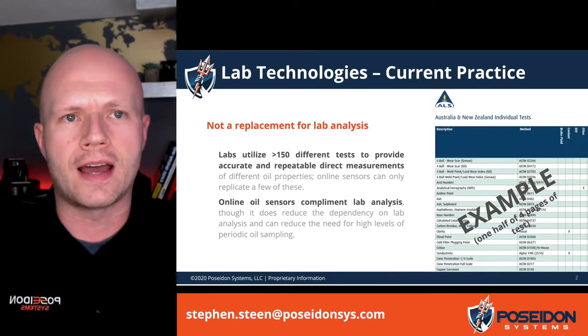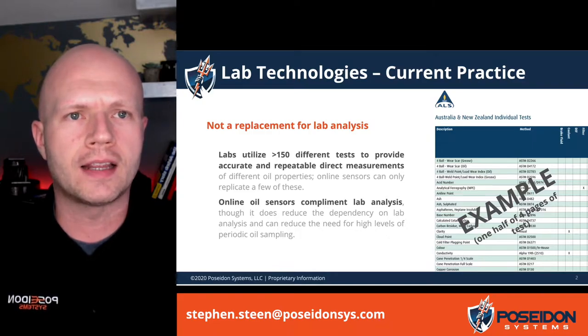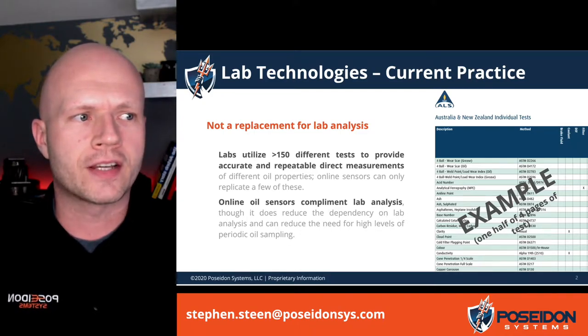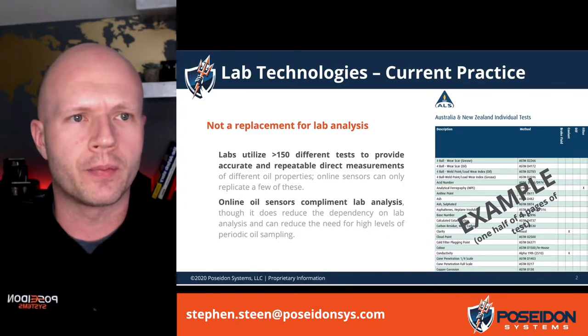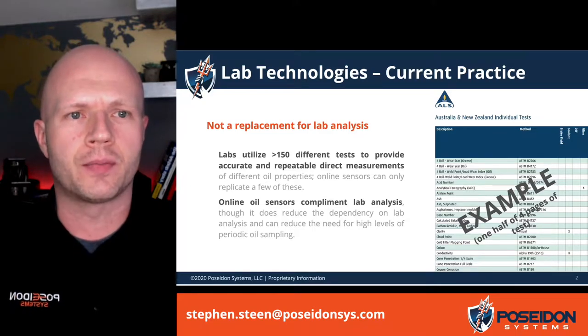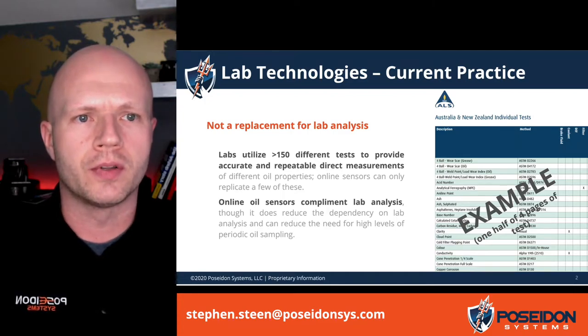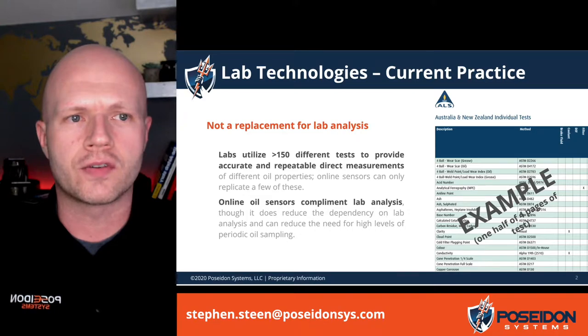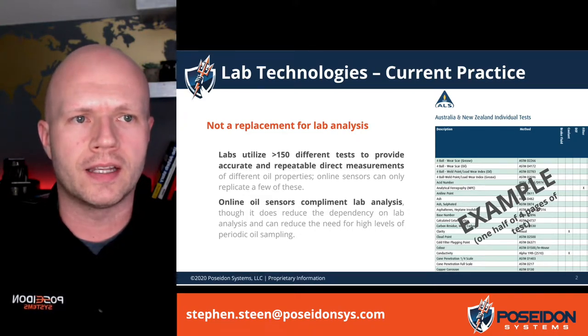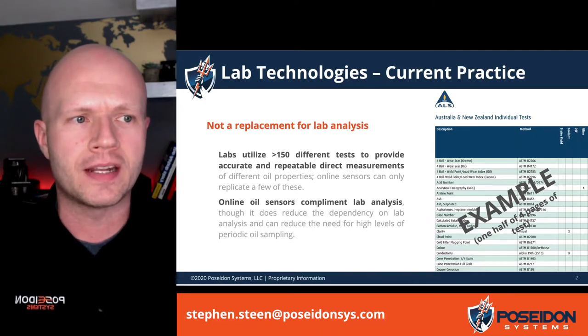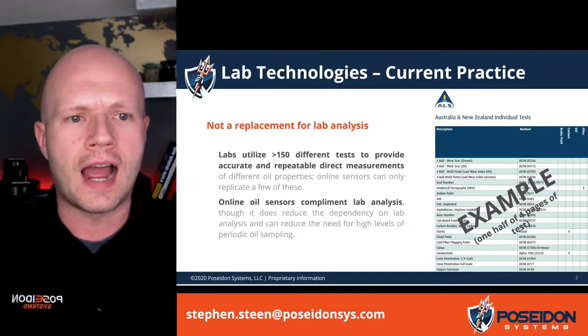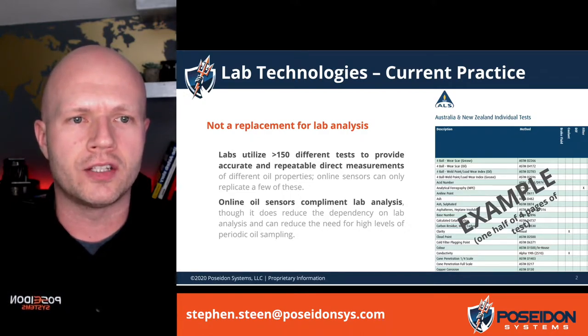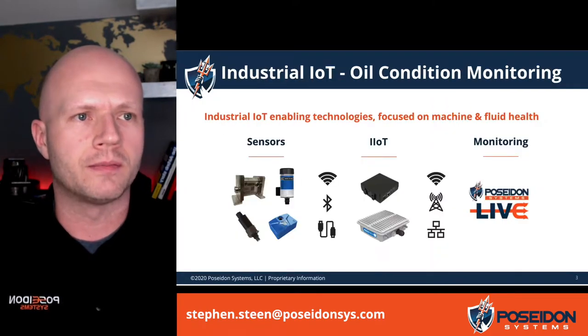A little bit of background — everyone is familiar with lab sampling as a practice for oil condition monitoring, and we want to highlight that online sensors are not a direct replacement for that lab analysis. On the right hand side you can see a short excerpt from one of the partners we work with — it's just a half page of roughly four pages of tests, and they utilize more than 150 different tests to provide those measurements. Those are very accurate, direct, repeatable measurements for different oil properties, whereas online sensors can only replicate a couple of those online. In other cases they are trending related measurements to give an indication of whether something is wrong with the oil. But it is very good because it complements lab analysis in terms of reducing the dependency on lab analysis, as well as the need for high levels of periodic sampling. You can use the trending from online sensors as an analog for the periodic sampling that had been done in the past.